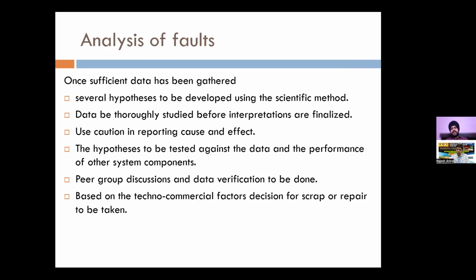Once all of the faults are analyzed in the light of my earlier observations, all data is gathered, all test results are established, and internal inspection is carried out, then you need to form several hypotheses which need to be explained in a very scientific manner, where based on our known physics, we should try to explain what could have caused the failure, what was the root cause, what it led to, and ultimately how we have ended up where we are. Once you form a hypothesis, it's also necessary that you should not stick to it. If some other data comes to light which contradicts your theory, you should not stick to your theory and try to negate the other data. You should go back to the ground level and reform the entire theory.